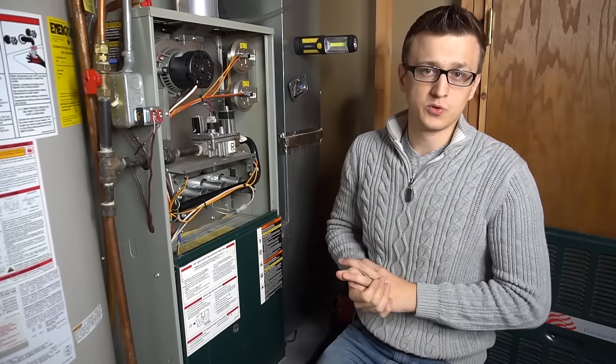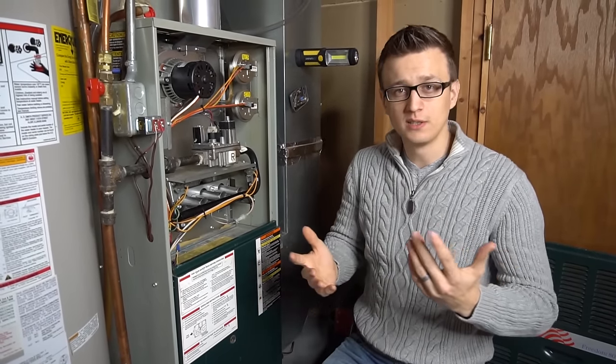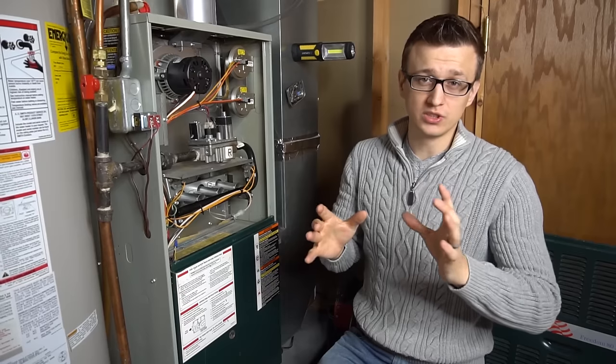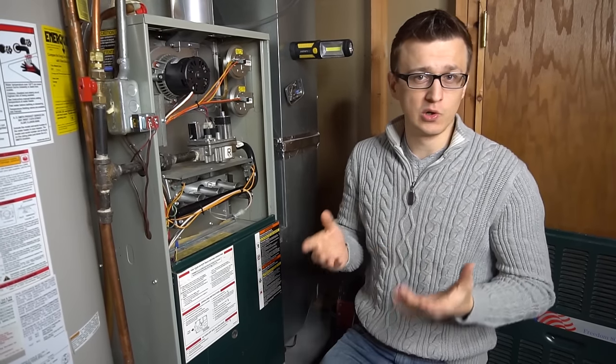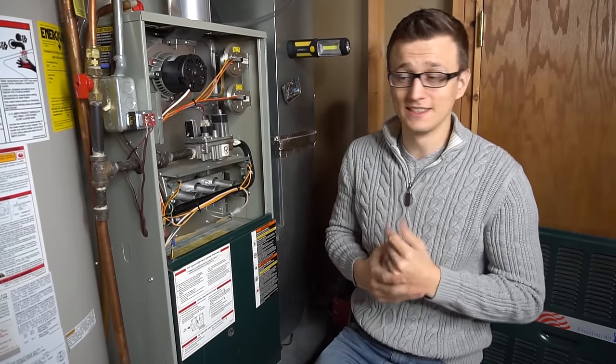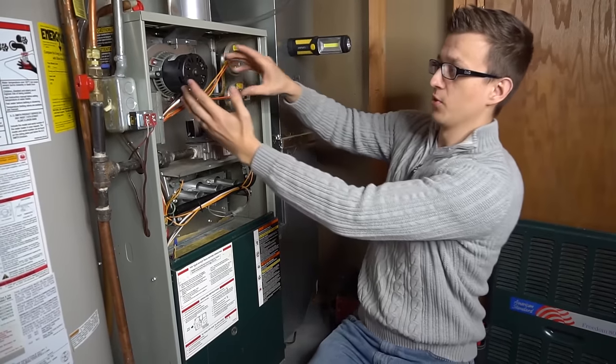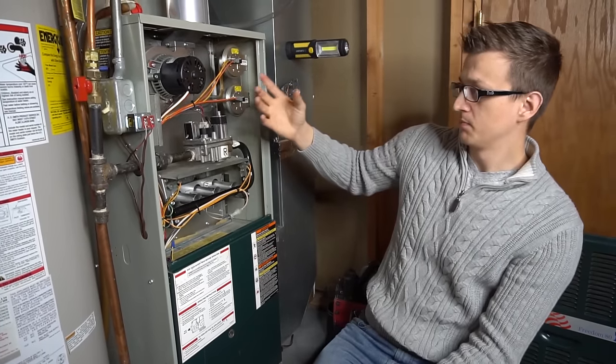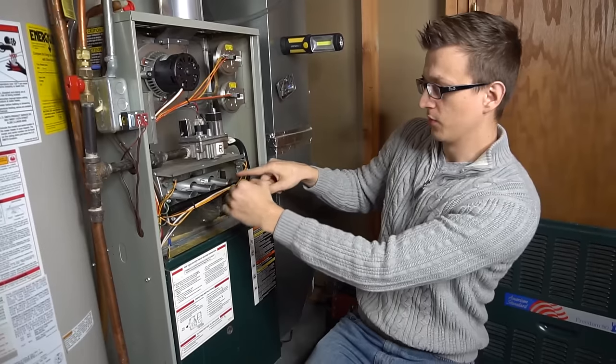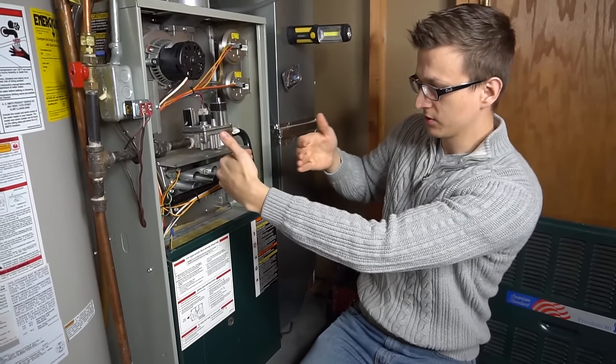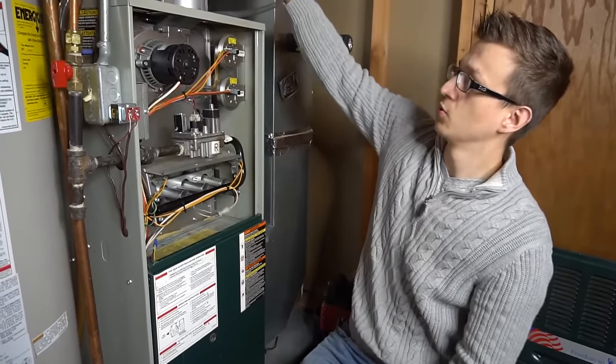If you have a flame rollout switch that has tripped, unfortunately that's usually a pretty bad sign. Flame rollout switches don't just trip for no reason. The way this works is the inducer motor is pulling a draft, so the flames kick on, it sucks them through the heat exchanger and blows them out the exhaust.